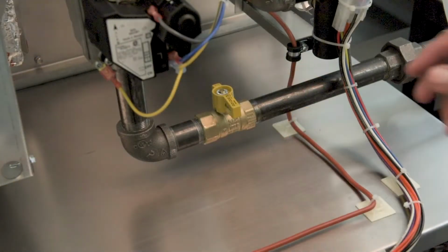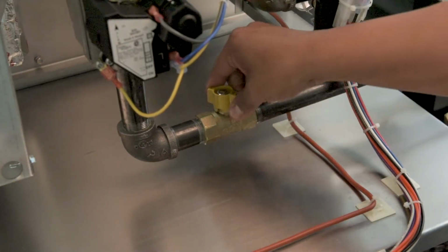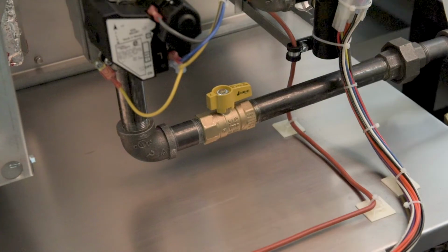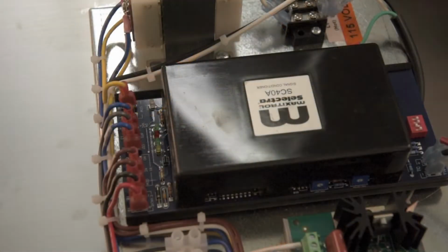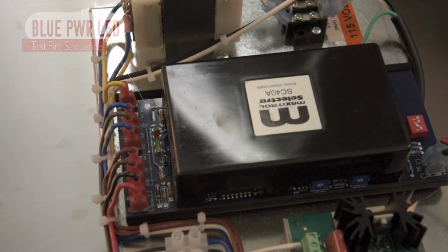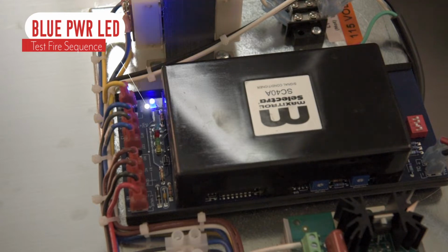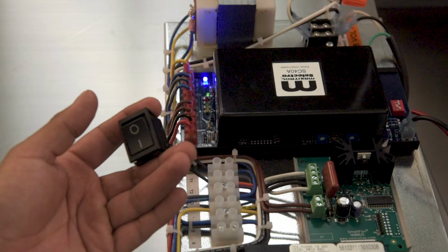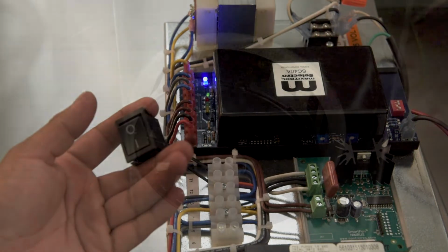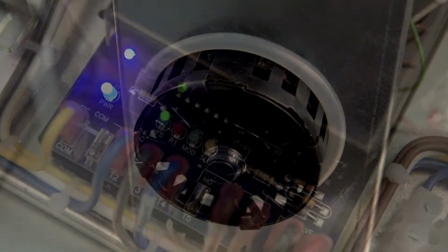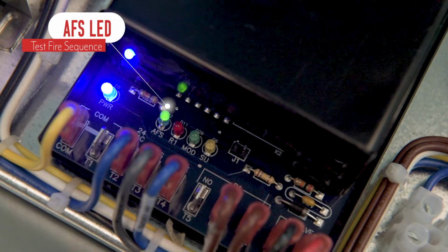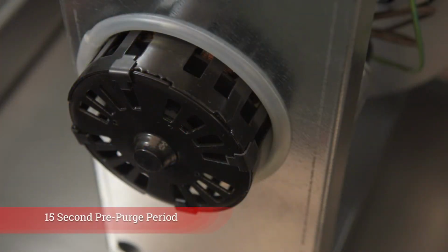To begin the test fire sequence, open the manual shutoff valve that is located upstream of the heater gas valves. Supply the source voltage to the heater control. The SC40 blue power LED will come on. Close the heat enable switch to initiate the startup sequence. The induced draft fan will start and the green AFS LED on the SC40 will turn on. The induced draft fan will run at high speed for a 15-second pre-purge period.